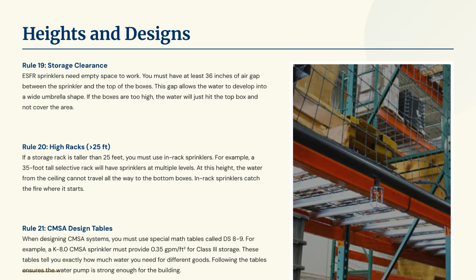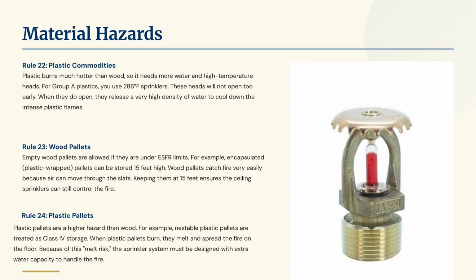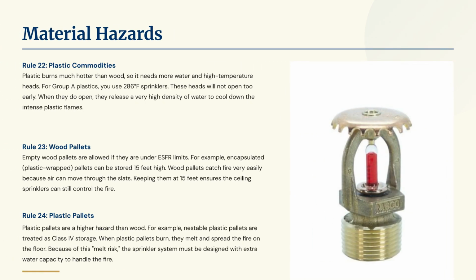Rule 21 requires using CMSA design tables, like DS 8 to 9, for water flow calculations. Rule 22 specifies high temperature heads and high water density for plastic commodities. Rule 23 allows empty wood pallets under ESFR limits. Rule 24 treats plastic pallets as a higher hazard due to melt risk, requiring extra water capacity.